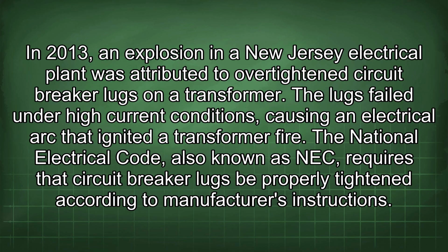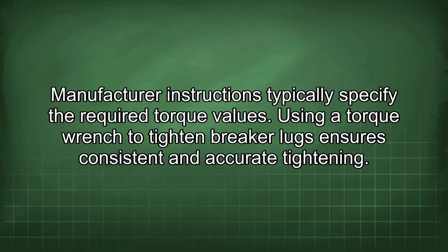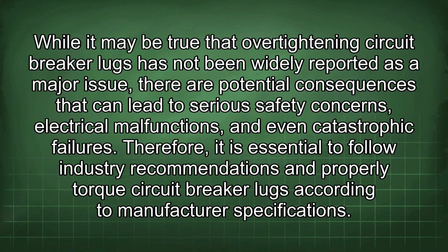The National Electrical Code, also known as NEC, requires that circuit breaker lugs be properly tightened according to manufacturer's instructions. Manufacturer instructions typically specify the required torque values. Using a torque wrench to tighten breaker lugs ensures consistent and accurate tightening. While it may be true that over-tightening circuit breaker lugs has not been widely reported as a major issue, there are potential consequences that can lead to serious safety concerns, electrical malfunctions, and even catastrophic failures. Therefore, it is essential to follow industry recommendations and properly torque circuit breaker lugs according to manufacturer specifications.